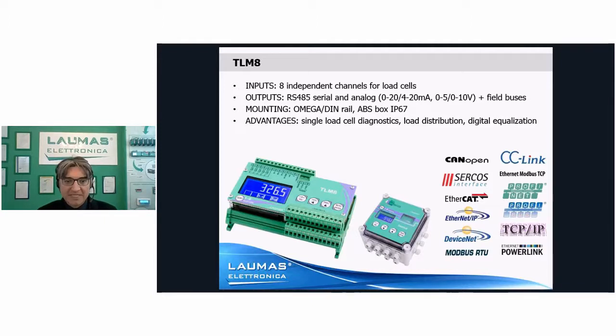Other features of multi-channel devices: they are all approved according to European Directive 2014/31/UE, so also the technical standards EN 45501 and OIML R76, so they can be legal for trade. All these devices can be connected to one of our W series indicators. In this way, all the multi-channel specific functions, the ones we have just seen, so diagnostics, equalization, and so on, can be controlled by the indicator. So everything works just as if the load cells were directly connected to the indicator.